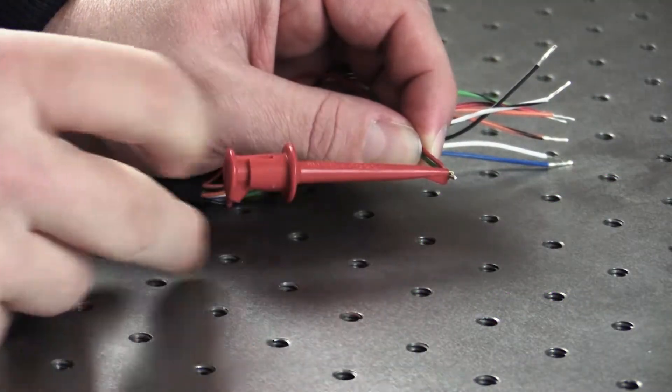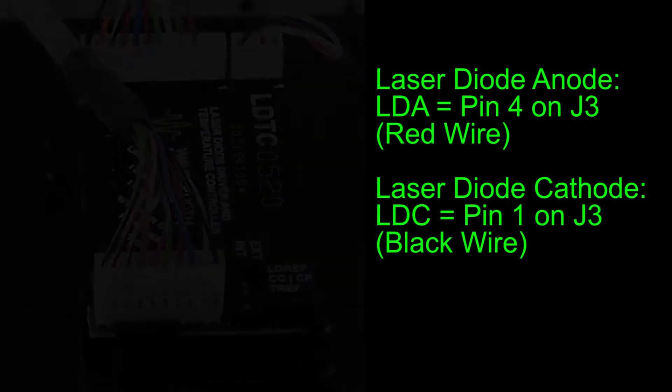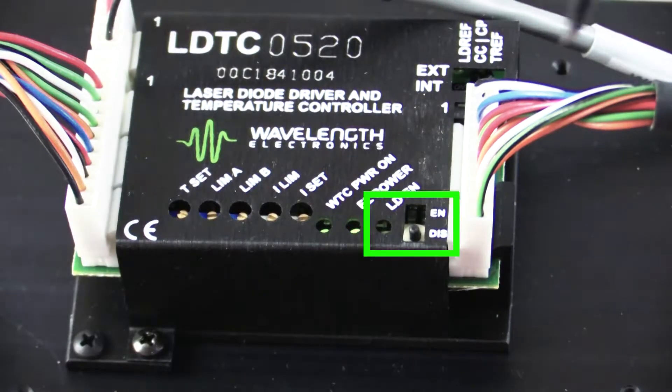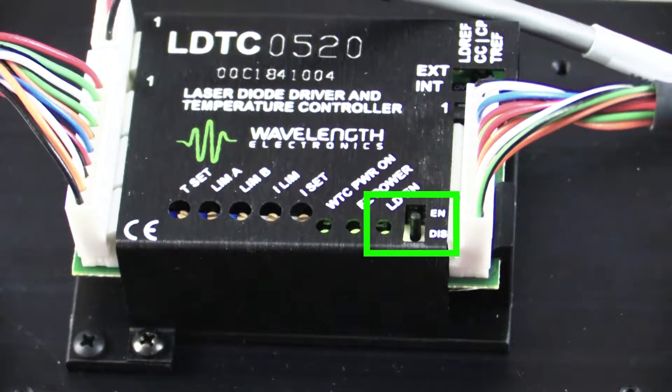Tie the LD Shutdown pin to ground. Next, connect the laser diode test load to laser diode anode and laser diode cathode. We are now ready to enable laser diode current by setting the laser output switch to enable. The LD Enable LED will illuminate green.